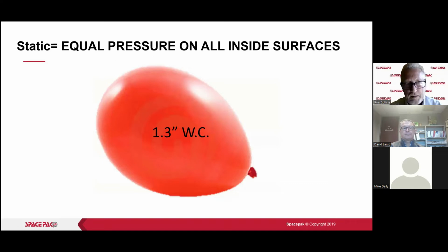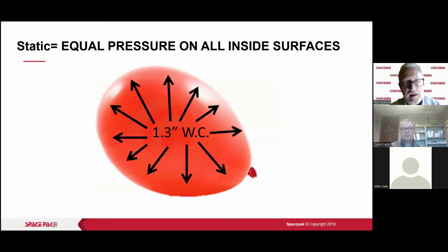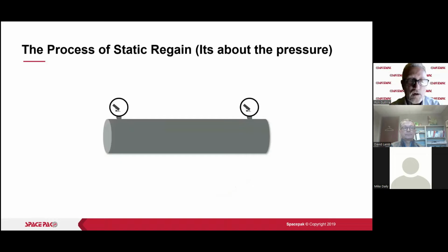Equal pressure on all sides of that balloon at 1.3 inches water column. All right, so that was blown up to 1.3 inches of water column, and that pressure is exerted on the entire inside area of that balloon. And if you've looked at the gas laws, they explain that as well. All right, we do the same thing with our ductwork. We use a process called static regain to blow it up like a balloon.